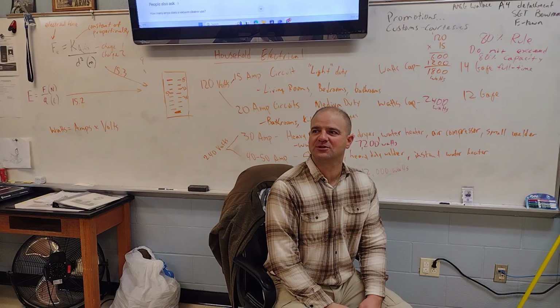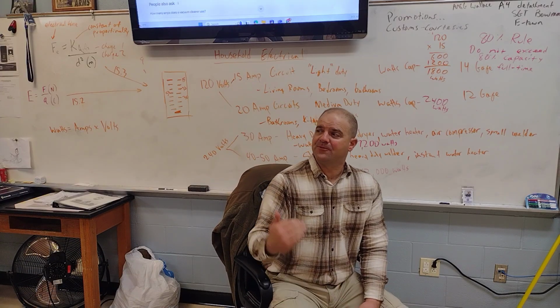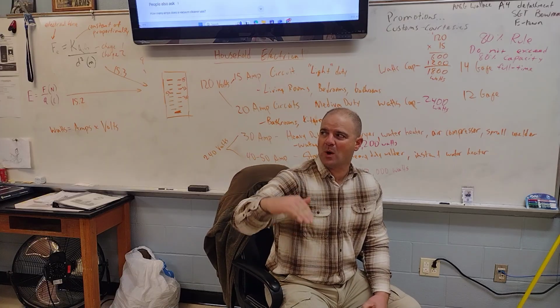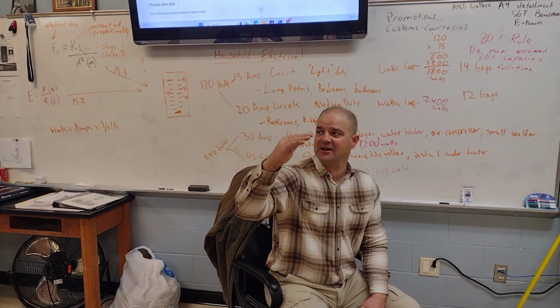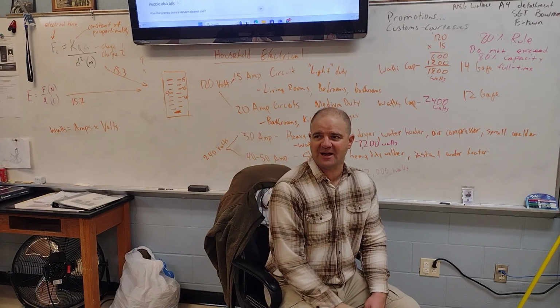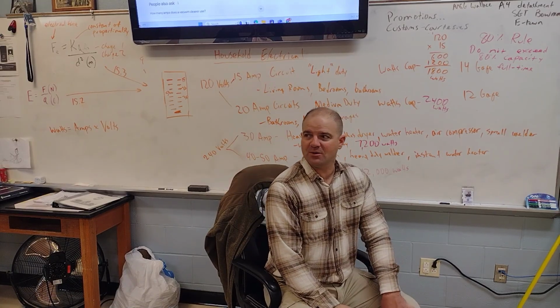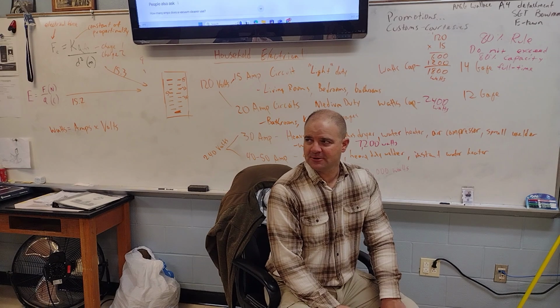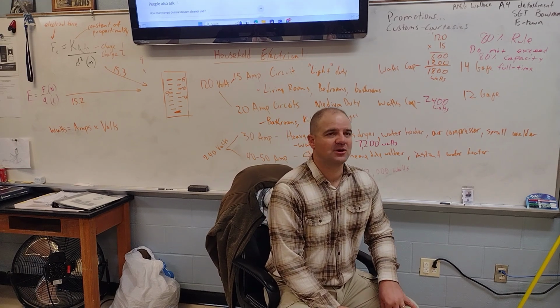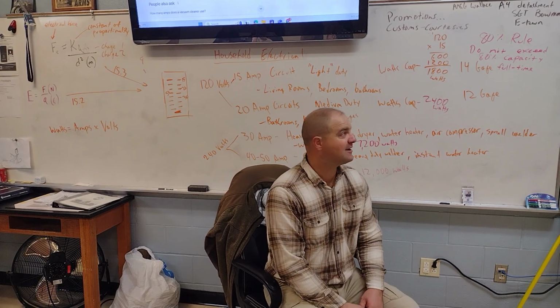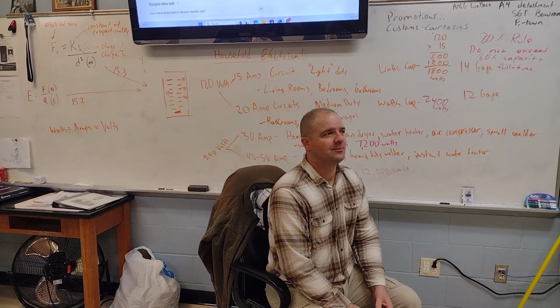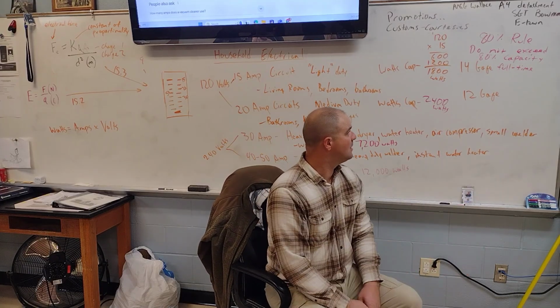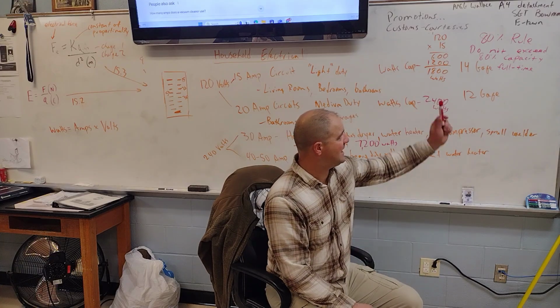What's that going to do to the circuitry, do you think? It's going to wear it out sooner, right? If you're constantly heating up that wiring to its maximum over and over again, so it's heating and cooling all the way up to its capacity, it's going to wear out the insulation faster, okay? Other components in that circuit might break down sooner. I think that's why they have that rule. It's to prolong the longevity of the circuit. So it's an 80% rule.